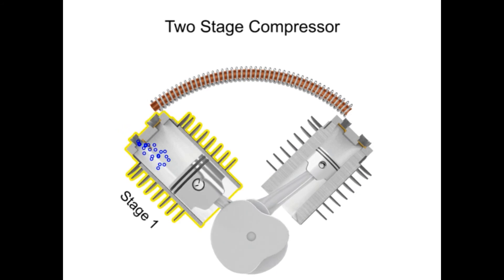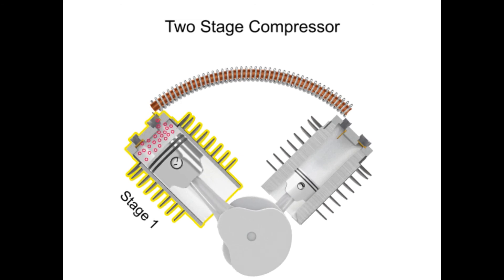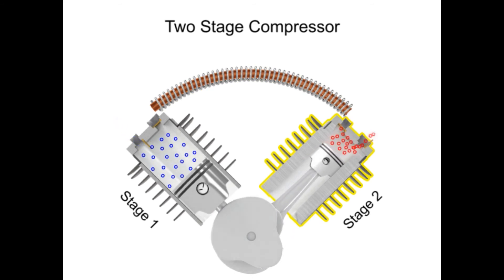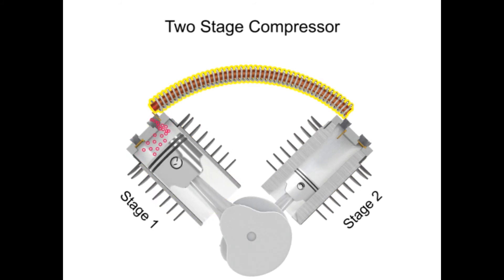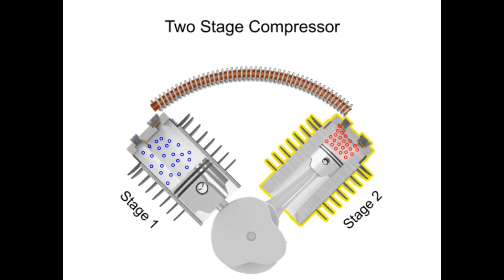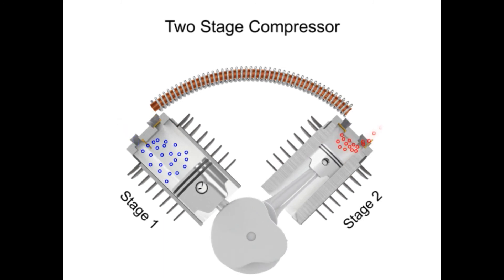The air is compressed in the first stage, which is typically the largest stage, then cooled, then compressed in a second stage. The hot compressed air from the first stage is conducted to the second stage through finned tubing, which is exposed to the air from a flywheel fan. After the air is cooled within the tube, the compressed air enters the second stage to be compressed even further. The compressed air entering the second stage is sometimes called supercharged air.